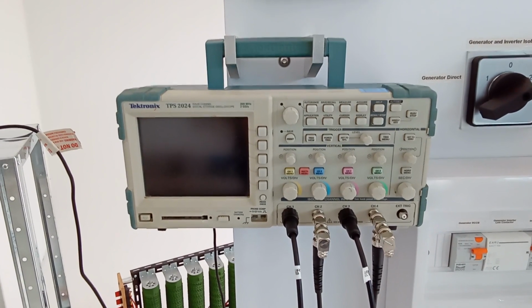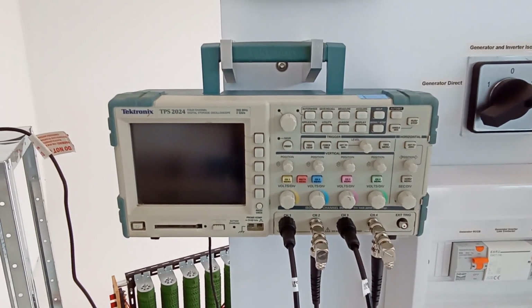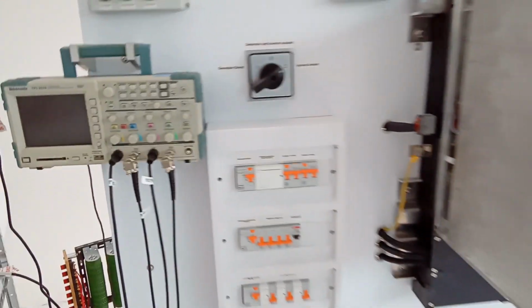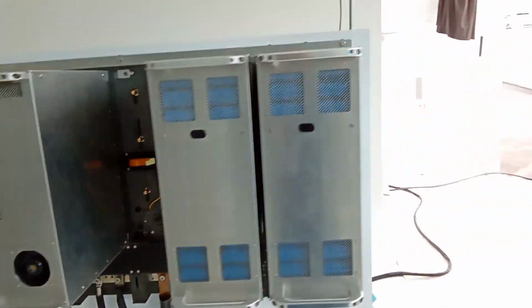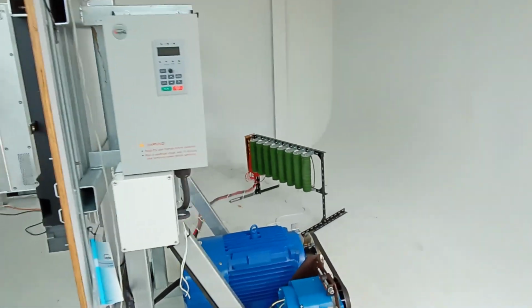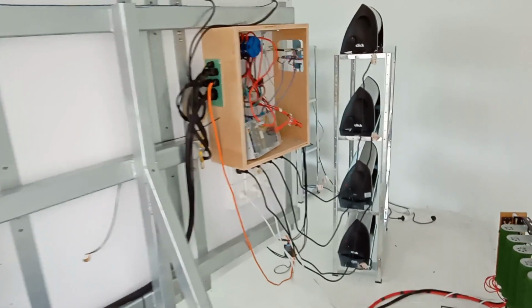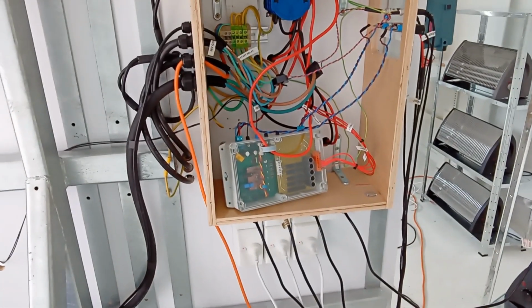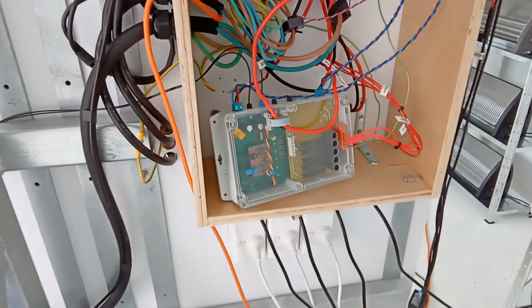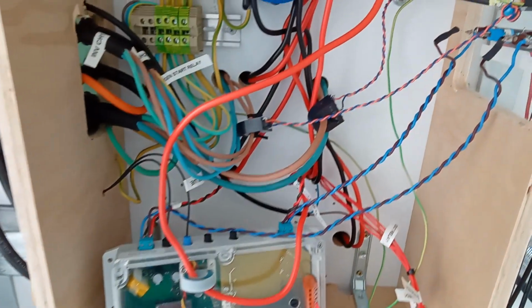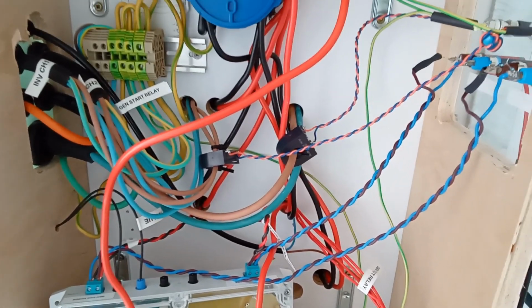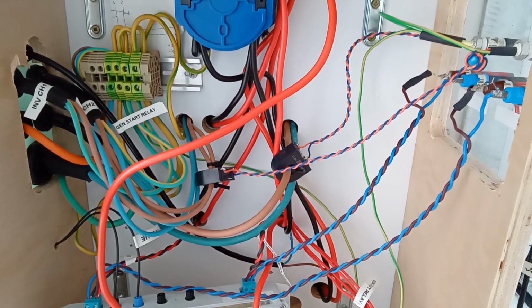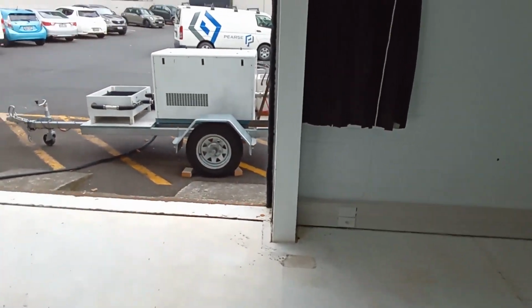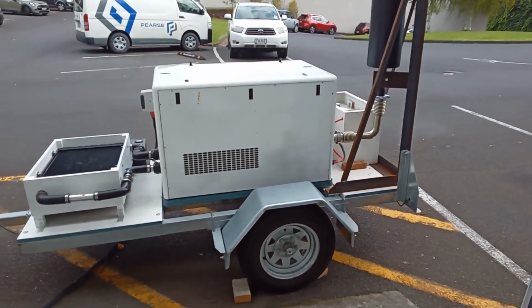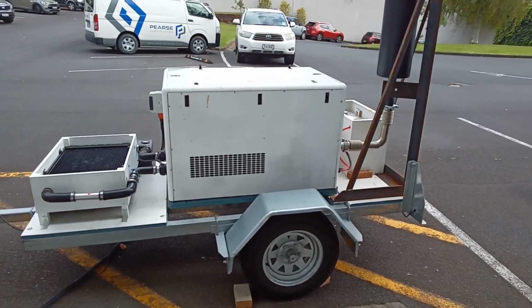Now, an oscilloscope for monitoring the inverter output voltage, the generator output voltage, inverter current and generator current. Around the back we have our generator controller that has a Hall effect current sensor on it. You can see the red wire going through it, and also current transformers on the inverter phase lead and the generator phase lead for showing the currents on the oscilloscope. Out here we have a Northern Lights 10 kilowatt marine generator set up to run on land.